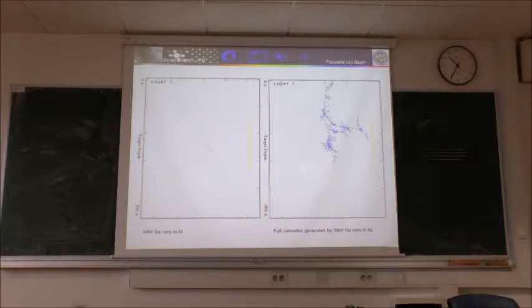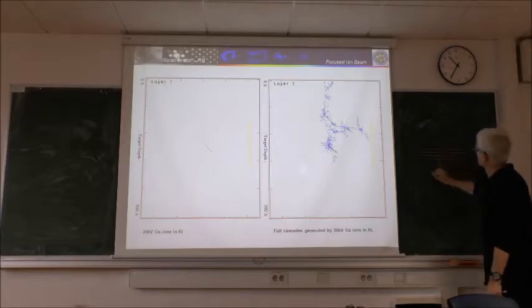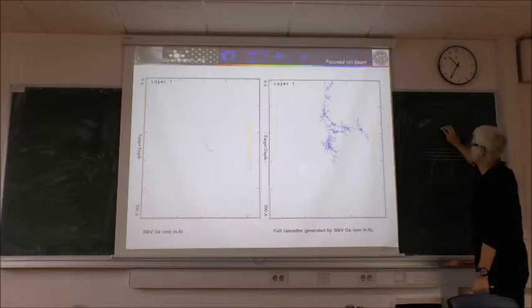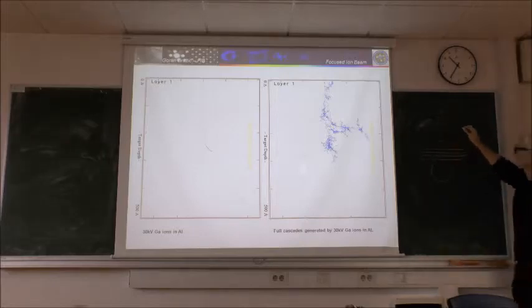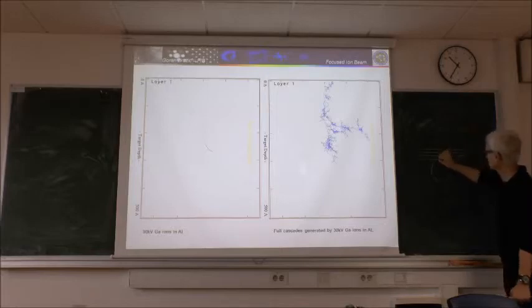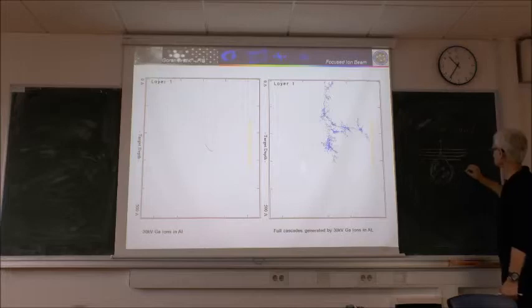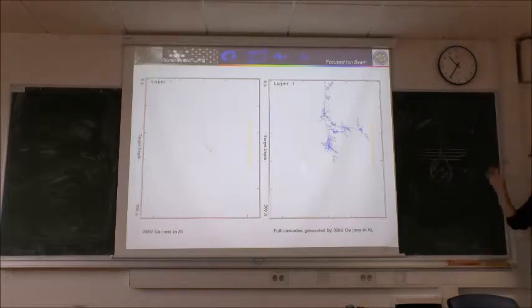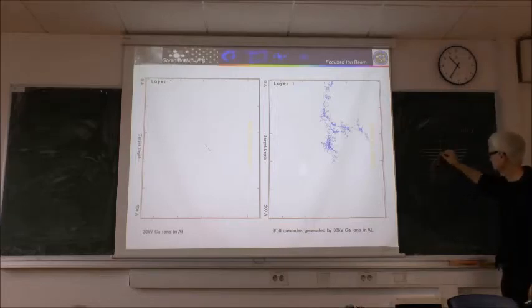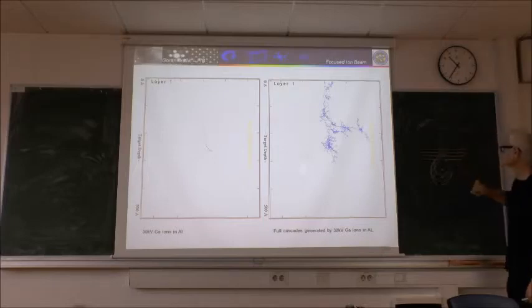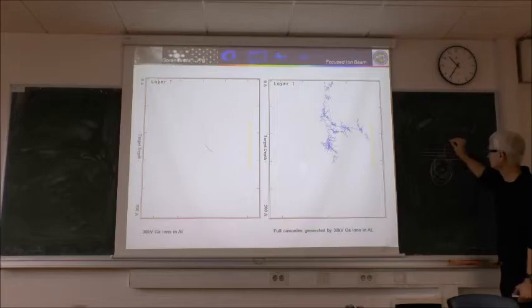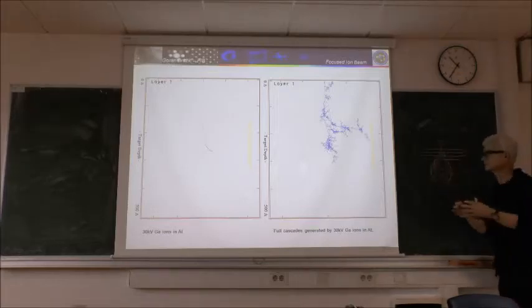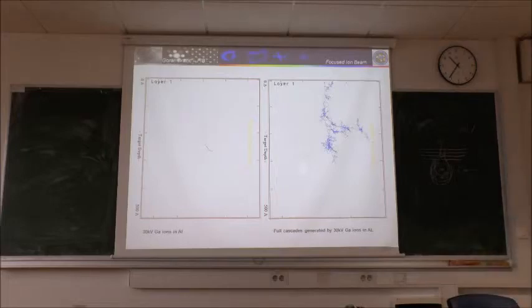What is the depth? In scanning, if you remember, the scanning electron microscope, this famous volume. So you might have here a 5 or even less, 1 nanometer sized electron beam. But if you are using 20 kilo electron volts of energy, at the end you will get a signal from 2 micrometers, depending on which type of signal. The worst resolution is X-rays. Slightly better are backscatter electrons, even better are secondary electrons, but still, doesn't matter the diameter of the incident electrons, you always have a much larger interaction volume. And this interaction volume is, of course, also very important and interesting here.